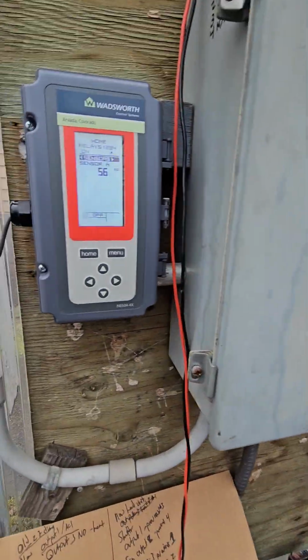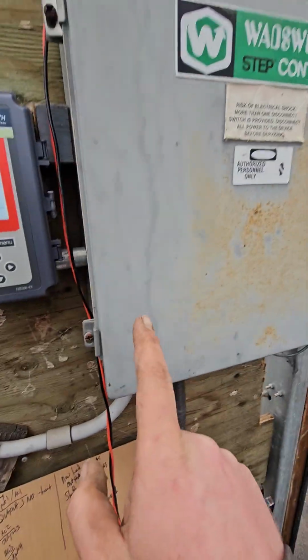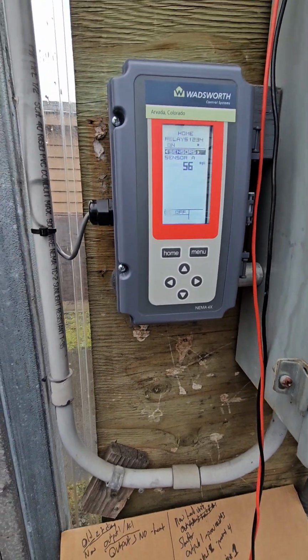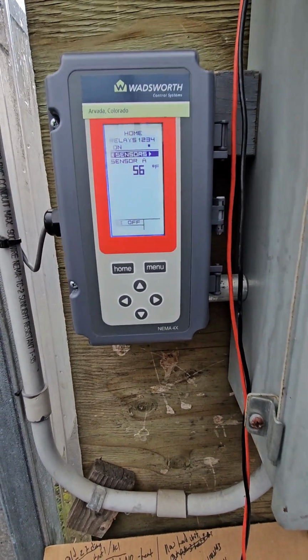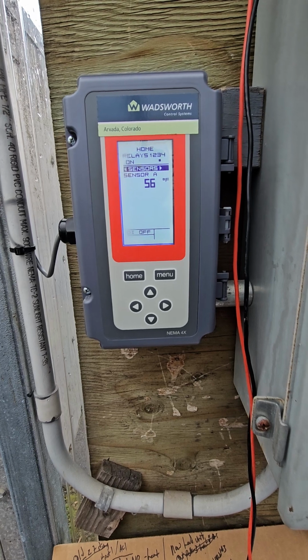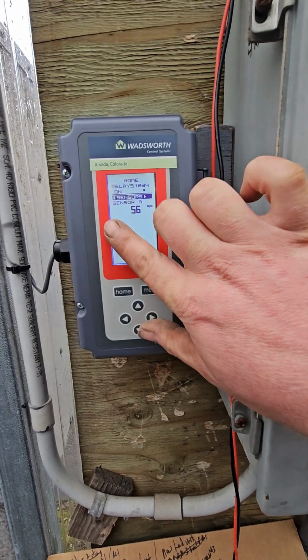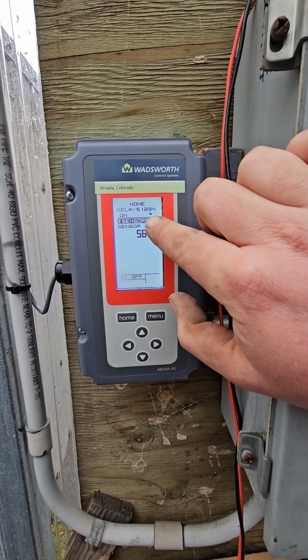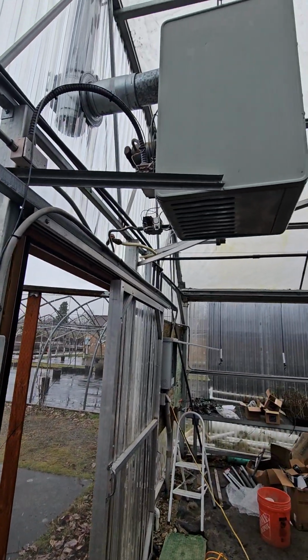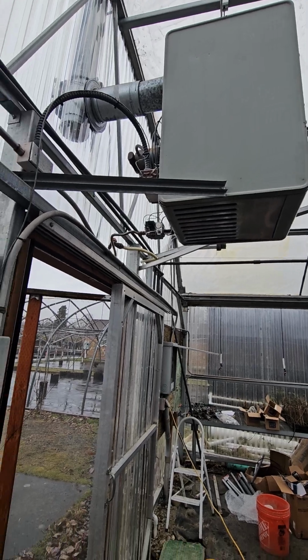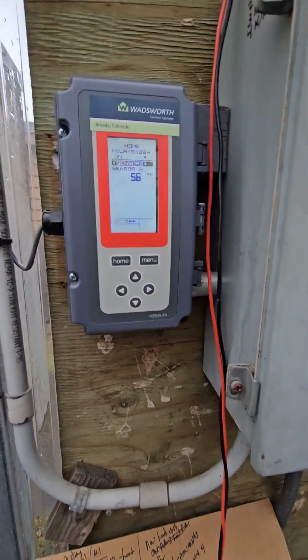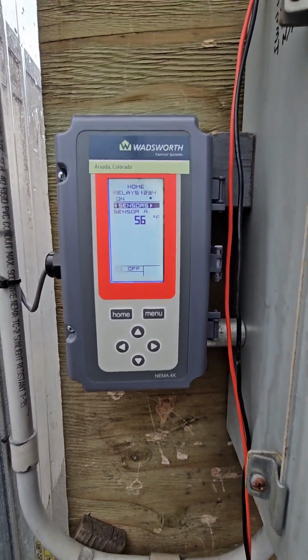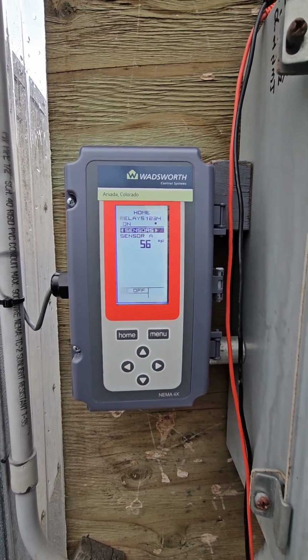We're not going to have this open because we got multiple power sources inside that, and right now we have power on in there. So right now, the only relay that's active is relay or output number 3. Output number 3 is for that heater that runs on propane, but they don't want to use it. This is for native plants, and they said it burns too much propane, so we're not going to worry about that.